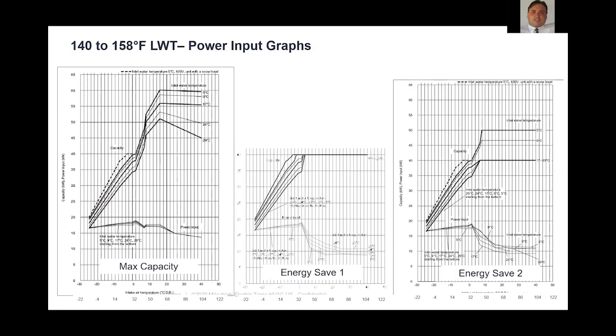And so you'll see charts in manufacturers' data, and obviously this is based on Mitsubishi again, that represent peak capacity output versus power input. And that's what we're looking at here. So you have these three different modes in the case of Mitsubishi. These top set of curves are your capacity output. And I apologize, this is all in KW because this is how the factories in Japan chart everything. But your top set of curves are maximum capacity, and your lower set of curves are power input.